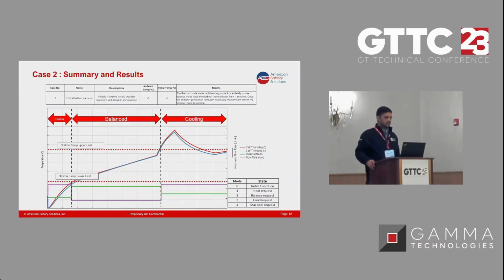Let me explain these optimal temperature limits. As I said earlier, the batteries must always be in the optimal temperature zone in order to operate safely and efficiently. So there's a lower limit and an upper limit, and the purpose of the BMS is to maintain cell temperatures within this limit.